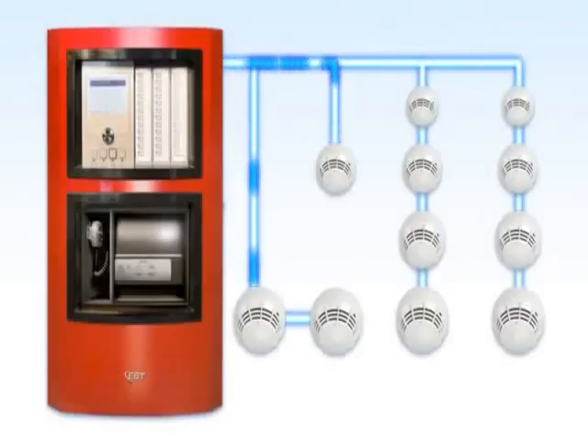The devices themselves now, instead of just turning on and off like they used to, can actually send information to the processing unit. It can give us what's called an alert status to say, hey, someone needs to come and check me. That way, instead of rolling our own fire brigade, now we can just send a specific runner to go check. Where is that detector located? Go look at it and say, oh yeah, it's dirty. So we can just remove it, clean it, put it back in, and no one's the wiser.